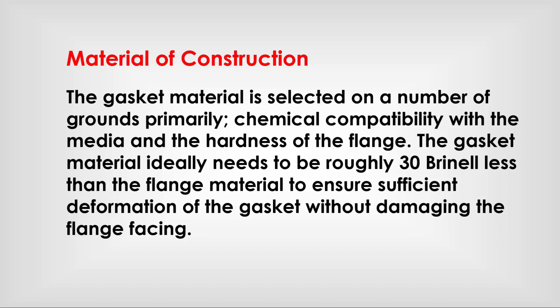Material of construction: the gasket material is selected primarily on chemical compatibility with the media and the hardness of the flange. The gasket material ideally needs to be approximately 30 Brinell less than the flange material hardness to ensure sufficient deformation of the gasket without damaging the flange facing.